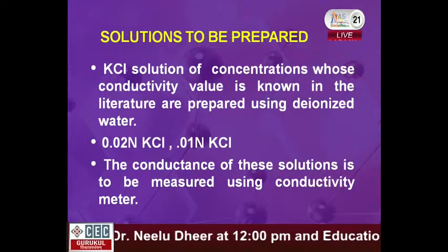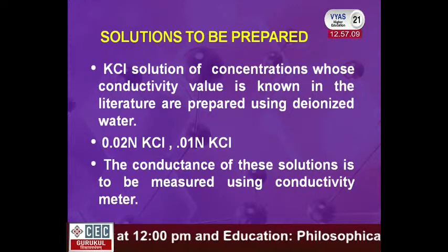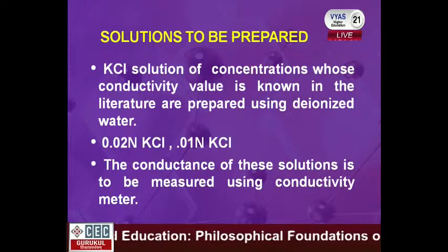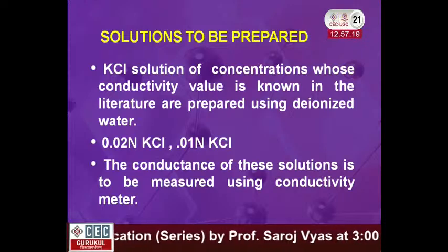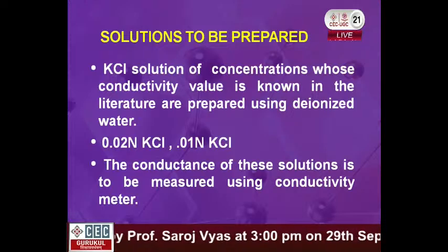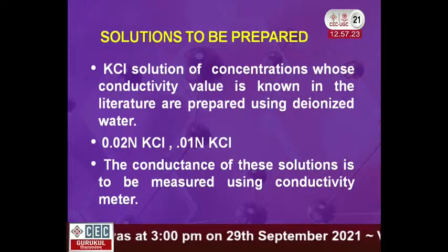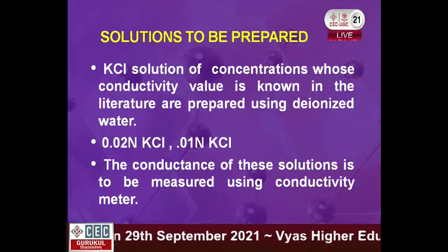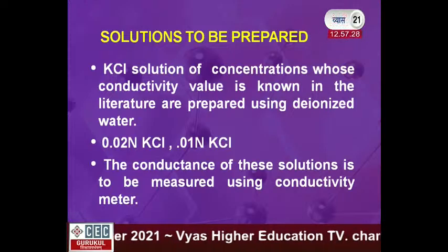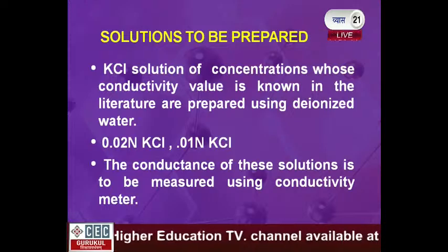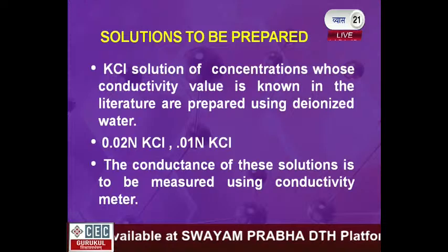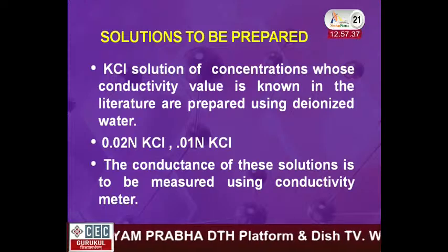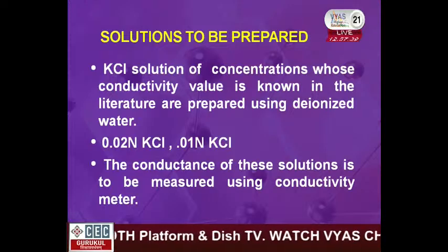Solutions to be prepared: KCl solutions of concentration whose conductivity value is known in the literature are prepared using deionized water. The concentrations of KCl solutions to be prepared here are 0.02 normal KCl and 0.01 normal KCl. The conductance of these solutions is to be measured using conductivity meter.